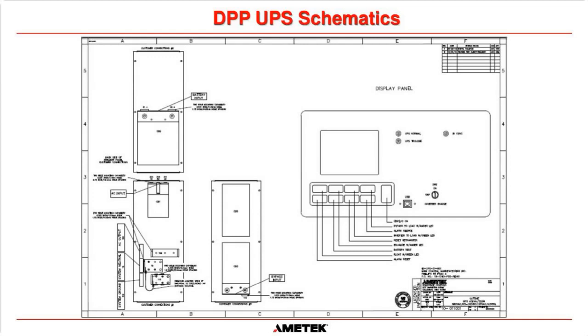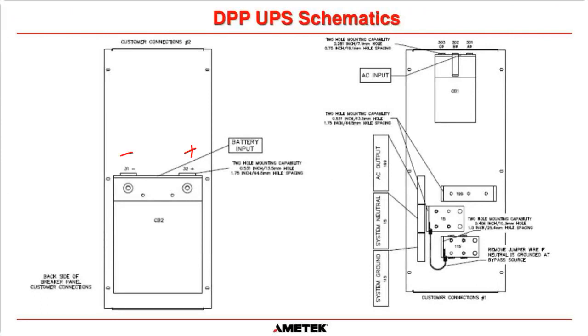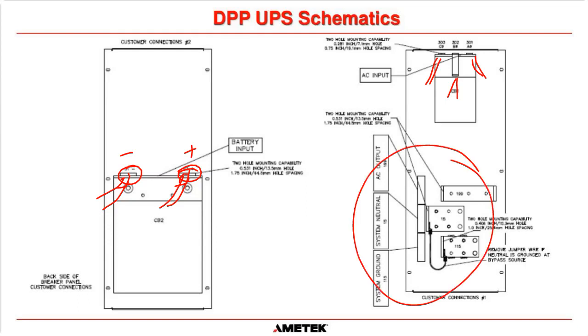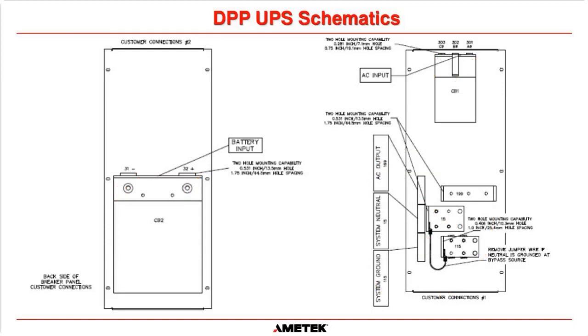And this diagram shows you where your connections should be made. Okay, I think I zoom in. So we've got our positive and negative cables going on here. You can't see it very well, but this is actually a bus bar tab coming from the back of the breaker itself. That is where you connect your negative cable from the battery, and that is where you connect your positive cable from the battery. Okay. Same with your AC input terminals, A phase, B phase, C phase on the tabs on the back of the AC input breaker. And then for the loads, your load is connected to these terminals down here. So the AC output goes here, 15 is your neutral. There's your system ground. So it gives you all the customer connections so you can tell your guys where to connect them.